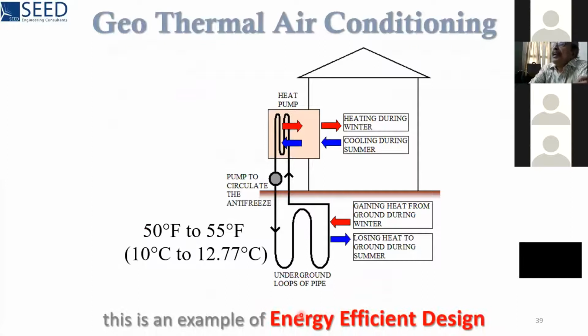Now this is geothermal air conditioning. If you go below Earth, the subsurface temperature of the Earth is always constant, between 50°F to 55°F. Your Mother Earth is a great heat sink. Where has this heat come from? That is from the sun. The sun's heat is absorbed by the Earth, and it is always at a constant temperature. There is not much difference in this temperature between winter and summer. It is almost constant in this particular range. Any amount of heat energy you supply to the Mother Earth, it will absorb without much difference in its temperature, within the range of 50°F to 55°F.